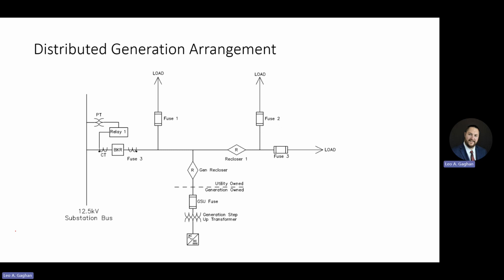So this may be a typical arrangement they might see. This comes off a 12 kV substation bus. It's got a breaker. It's got a relay. You can see there we've got the backbone, the distribution circuit, with our typical things that we've been talking about: fuses, reclosers, load. And then we can see we've got a generation recloser. And then we have a point of demarcation, which goes between what's utility owned and what's generation owned. This one has a fuse going to a GSU that goes to an inverter. So just a good visual of a typical trend.